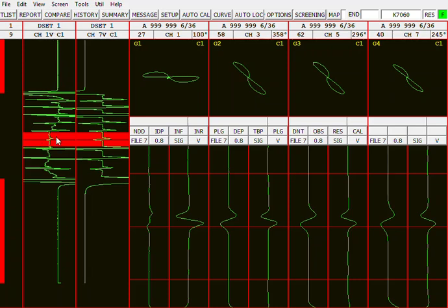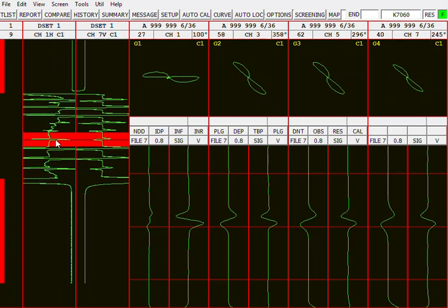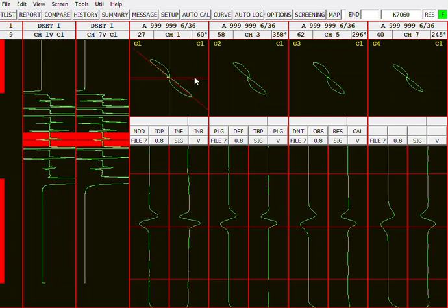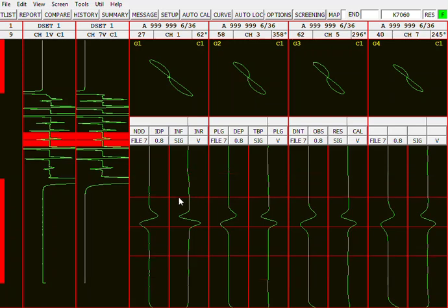On the vertical strip chart, I mean, sorry about that. Now if I switch over to the horizontal strip chart, what I gotta do, shift, middle click maybe, there we go. Now it sticks out a lot because that's a horizontal strip chart, and this signal has a large horizontal component here. But I'm gonna switch it back to vertical, and I'm gonna set the signal to the right phase, which is right about there. Now if I was interested in finding dents, dents have a horizontal signature.